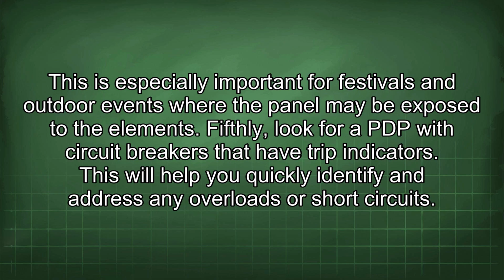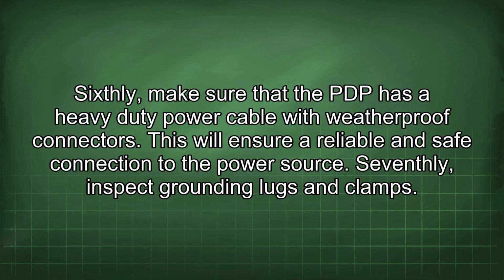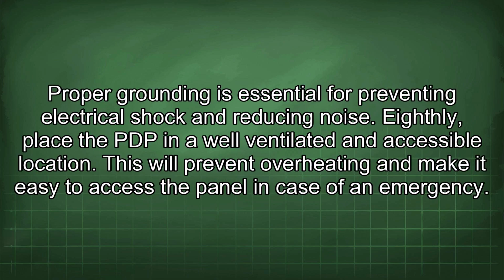Fifthly, look for a PDP with circuit breakers that have trip indicators. This will help you quickly identify and address any overloads or short circuits. Sixthly, make sure that the PDP has a heavy-duty power cable with weatherproof connectors. This will ensure a reliable and safe connection to the power source. Seventhly, inspect grounding lugs and clamps. Proper grounding is essential for preventing electrical shock and reducing noise.